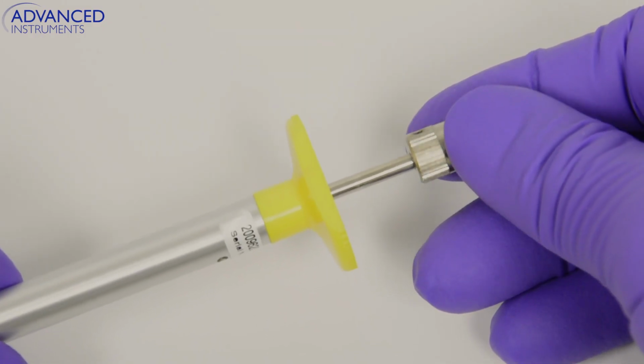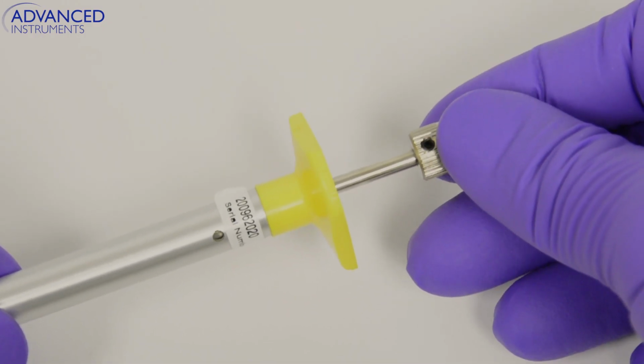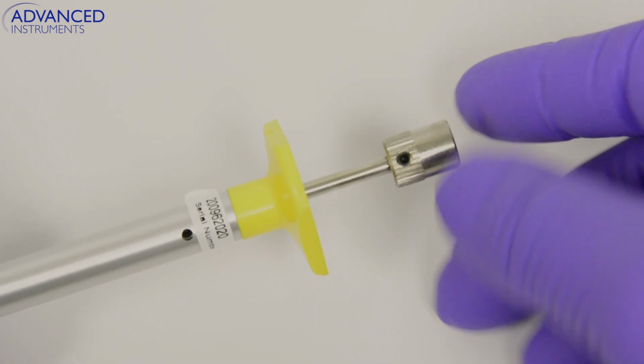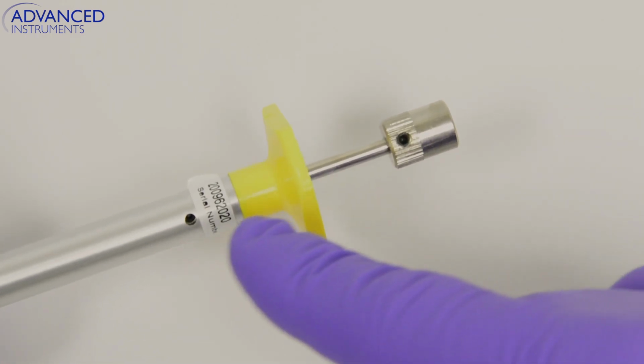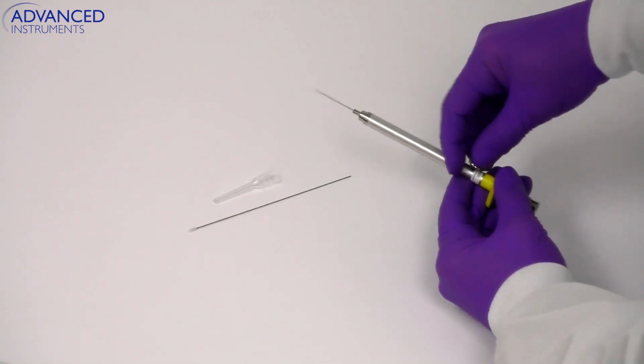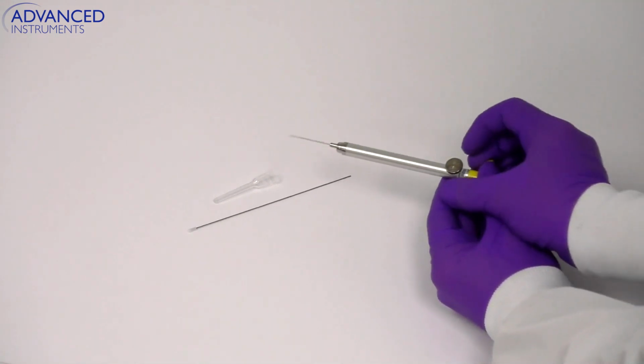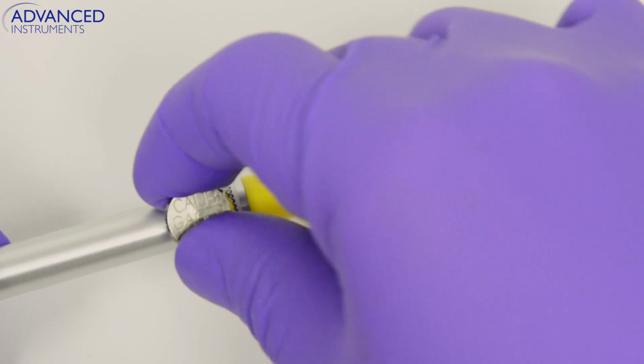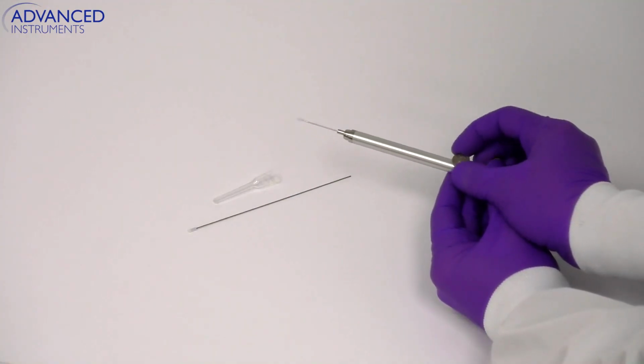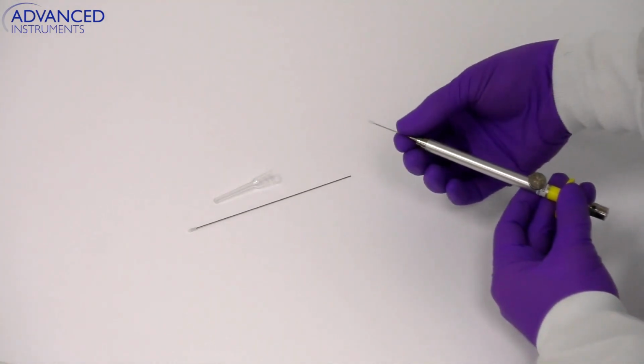Next, you'll rotate the sampler shaft until the calibration set screw appears beneath the access hole in the side of the sampler body. Place the key end of the calibration gauge into the access hole and turn counterclockwise. Carefully remove the old sampler wire and discard.